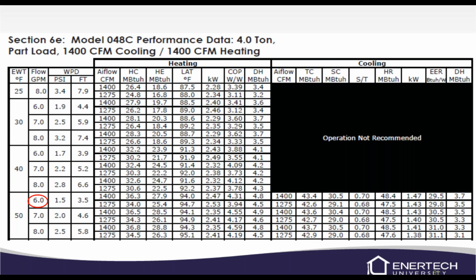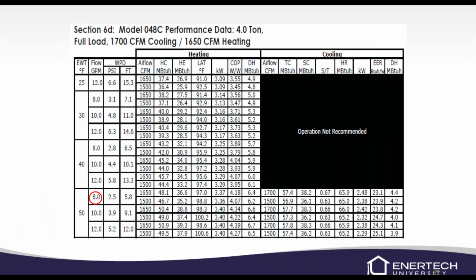So here we've got a 4-ton part load, 6 GPM, so 2/3 capacity, and full load. Again, here's a 4-ton unit, and they're using the 2 GPM per ton for this chart here. You will notice that there are 3 different flow rates listed in the chart. We have the recommended open loop flow rate on the first one. The second is the minimum flow rate for a closed loop, which is 2.25 GPM per ton, and the recommended flow rate on a closed loop, which is 3 GPM per ton.